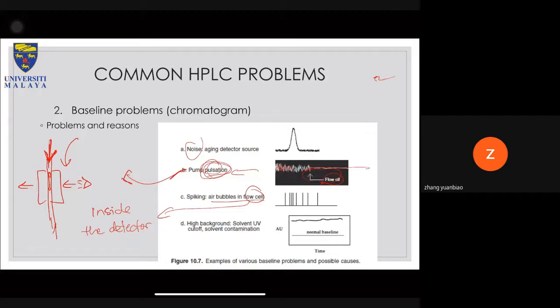Depending on what type of pump you have for your HPLC, it might normally be a sinusoidal pump, and even though you have a dampener, you might still see the pressure going up and down. While this happens, if a big bubble is present in your system, the bubble is simply moving up and down, passing through the light source. Therefore, you see random spiking happening any time of the day.